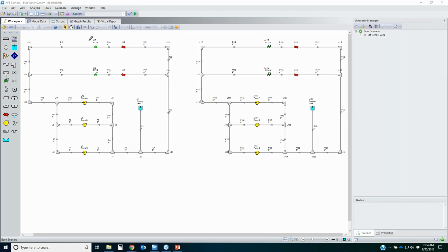Okay, so I need 1,500 here and 1,500 here. That means each pump is going to be delivering right around 1,000 GPM. Same idea, but instead I've specified 1,000 gallons per minute, 1,000 gallons per minute, and 1,000 gallons per minute. My peak hour base scenario operation is 4,380 hours. That's basically 12 hours a day, 365 days a year.